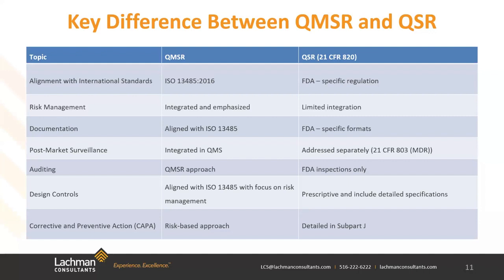From a documentation perspective, the QMSR is going to rely heavily on the ISO 13485 documentation framework, including the quality manual, risk management file, and more standardized formats, with a strong focus on documented procedures and records to demonstrate compliance, whereas the QSR requires detailed records as directed by the regulation itself. Post-market surveillance: QMSR emphasizes post-market surveillance and feedback systems in alignment with the EU MDR and the ISO 13485 requirements, and requires systematic monitoring of the device performance and customer feedback for continual improvement, whereas under the QSR, the post-market requirements are addressed separately under 21 CFR 803, the medical device reporting, and other parts not integrated within the quality management system.